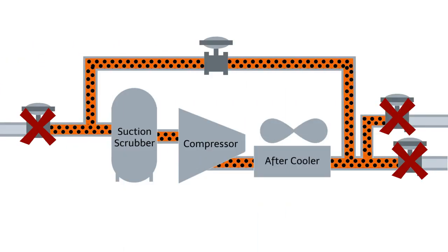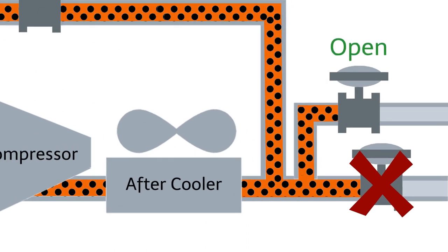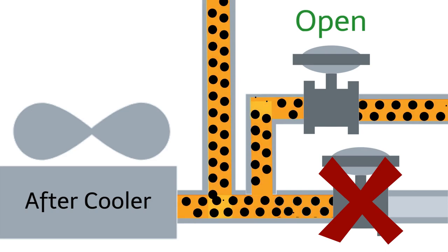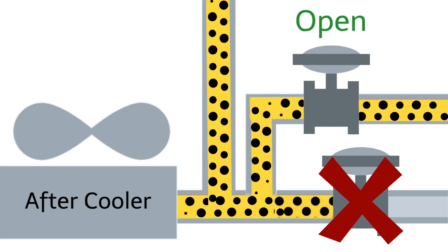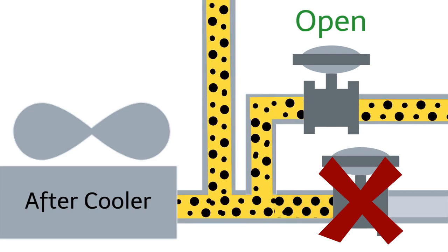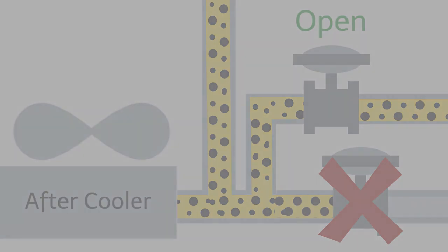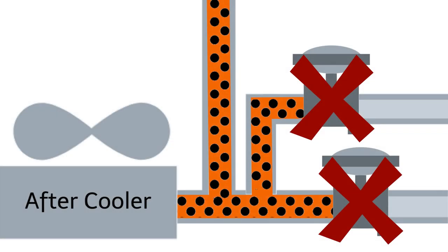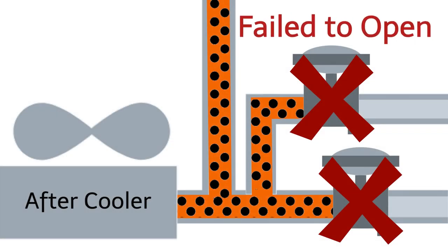We also have the blowdown line, which protects against settle-out overpressure by relieving pressure downstream of the compressor to the flare. This line should have opened when the shutdown was initiated. However, the control valve failed closed.